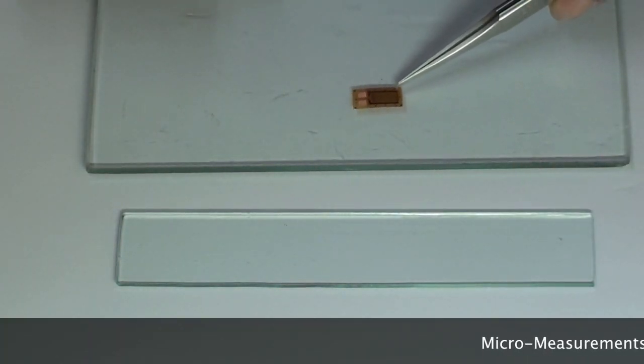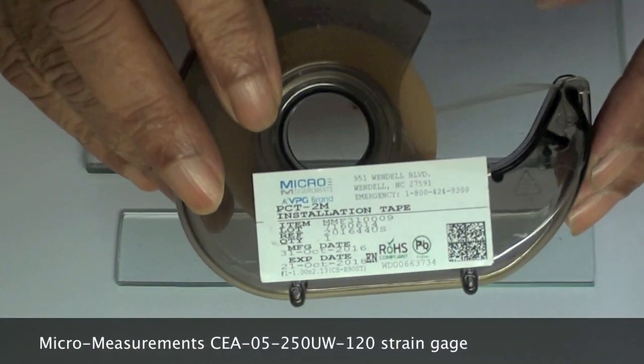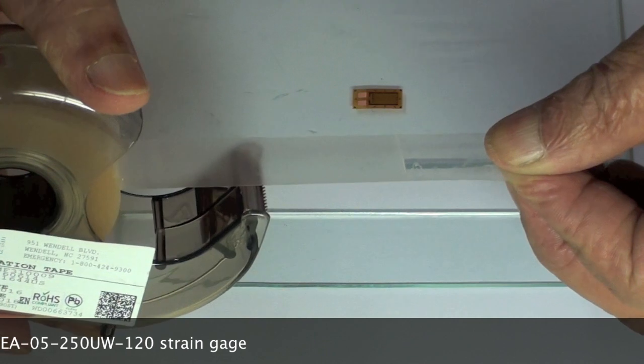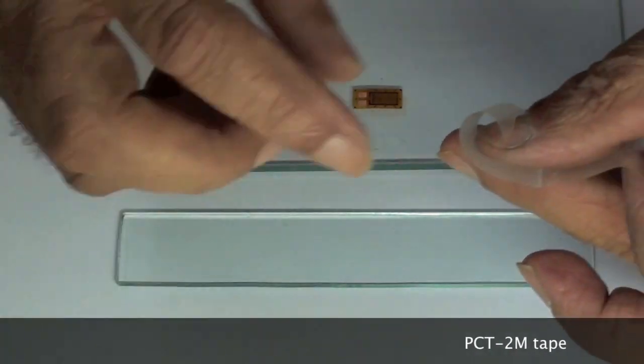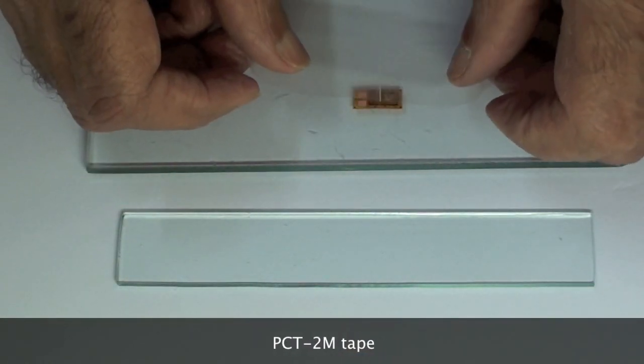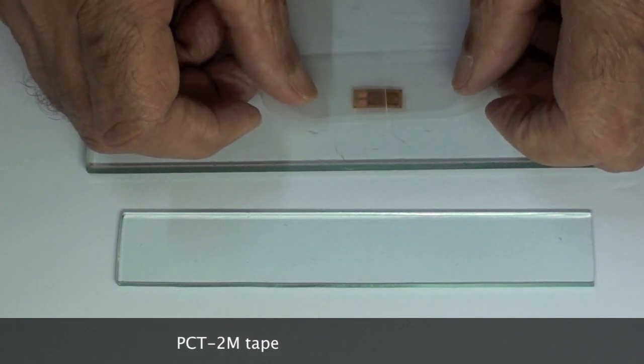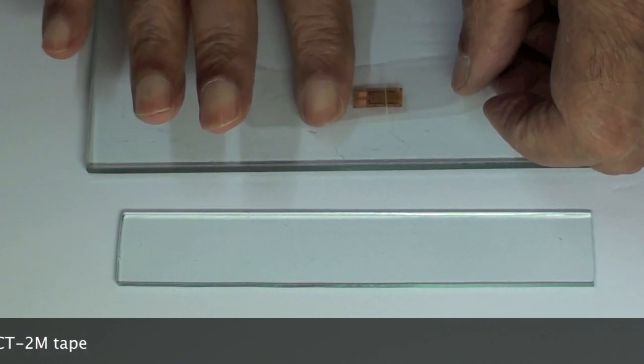To transfer the gauge to the beam, a special tape such as the PCT-2M tape is used as it does not leave its sticky mastic behind on surfaces. A length of 3-4 inches of PCT-2M tape is laid over the gauge and its edge is folded to make a handle to lift the tape again.